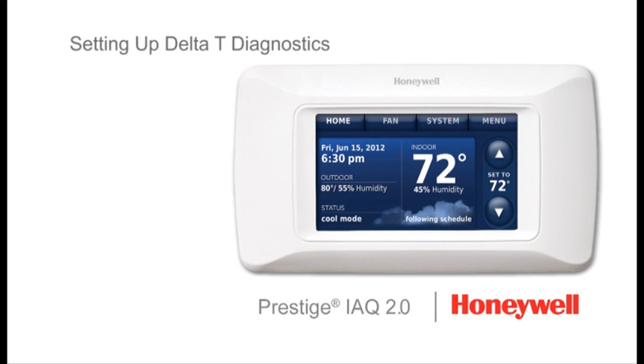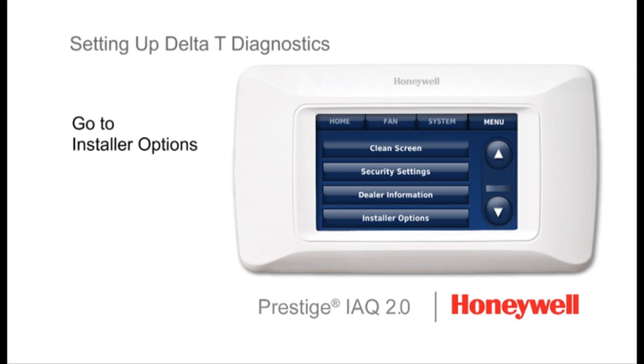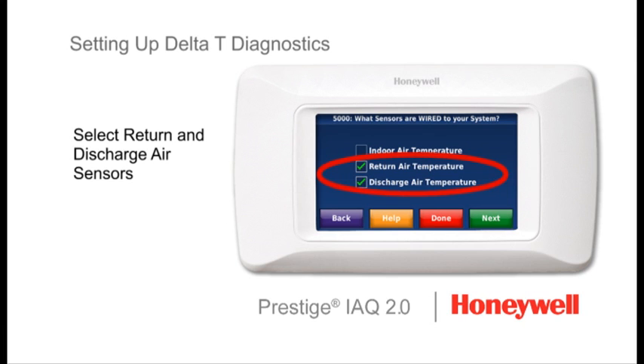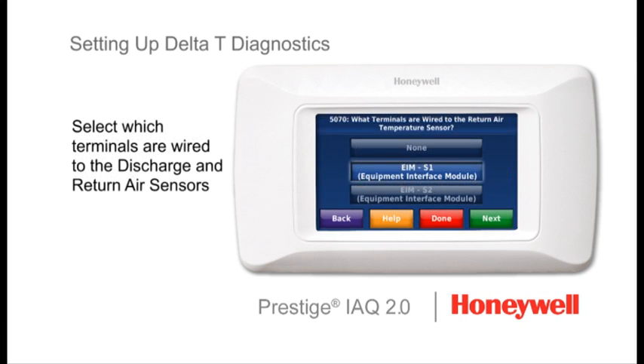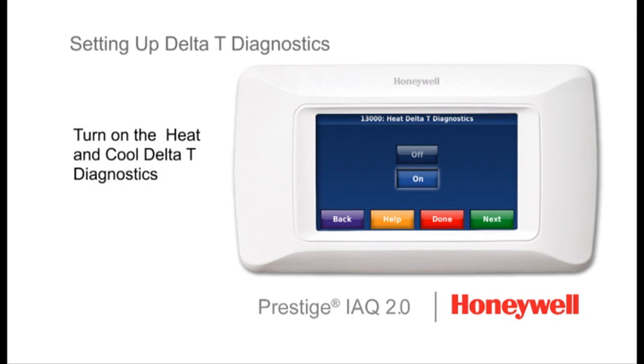To begin the delta T setup process, go to the installer setup screens on Prestige. The first step is to select the return and discharge air sensors. Step 2 is to select which terminals are wired to the discharge and return air sensors. The sensors are connected to the S1 and S2 terminals at the equipment interface module. And finally, you'll be prompted by the setup screens to turn on the heat and cool delta T Diagnostics.